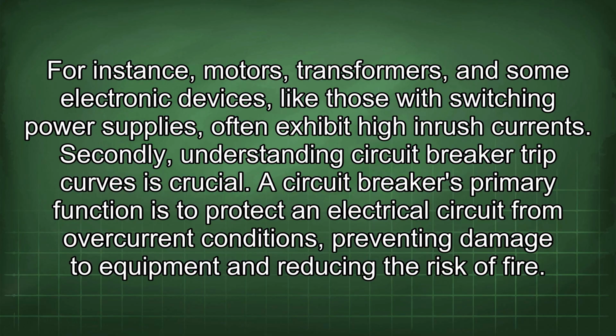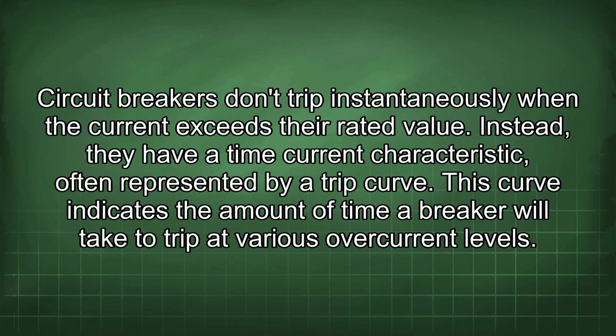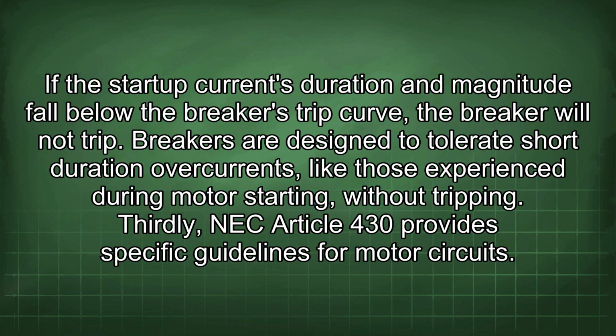Secondly, understanding circuit breaker trip curves is crucial. A circuit breaker's primary function is to protect an electrical circuit from overcurrent conditions, preventing damage to equipment and reducing the risk of fire. Circuit breakers don't trip instantaneously when the current exceeds their rated value. Instead, they have a time current characteristic, often represented by a trip curve. This curve indicates the amount of time a breaker will take to trip at various overcurrent levels. If the startup current's duration and magnitude fall below the breaker's trip curve, the breaker will not trip. Breakers are designed to tolerate short duration overcurrents, like those experienced during motor starting, without tripping.